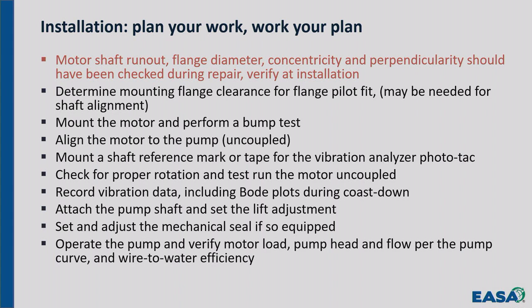Determine the clearance between the ID or OD of the motor flange and the ID and OD rabbet on the pump housing. Okay? So you do that with a micrometer or some measurement tool that will give you those dimensions. And you want to know what the clearance is. That clearance will determine the amount of horizontal alignment latitude that you have.